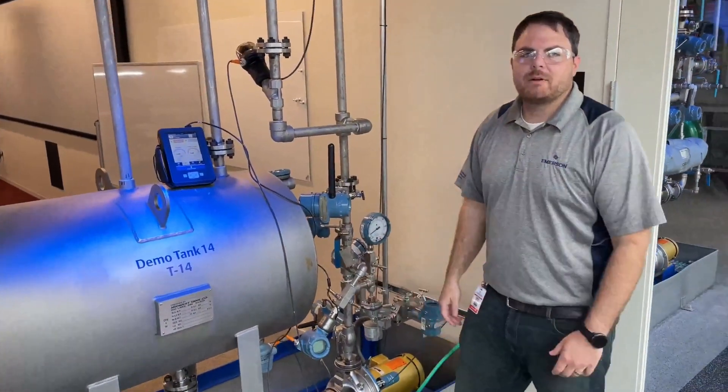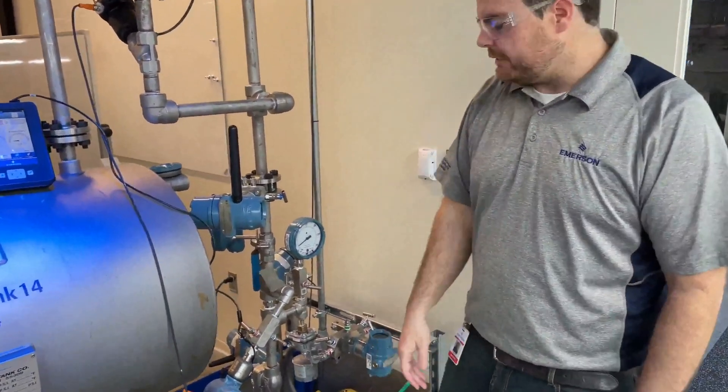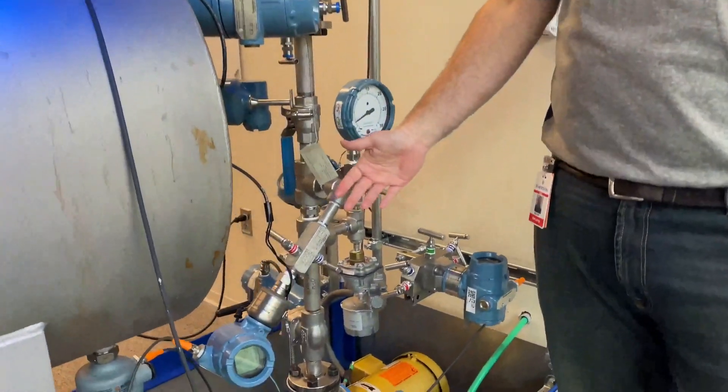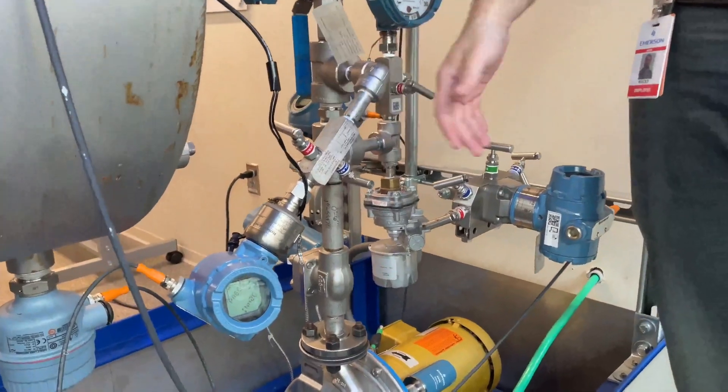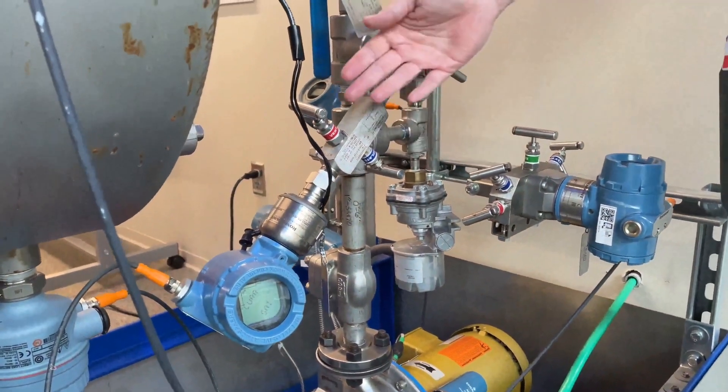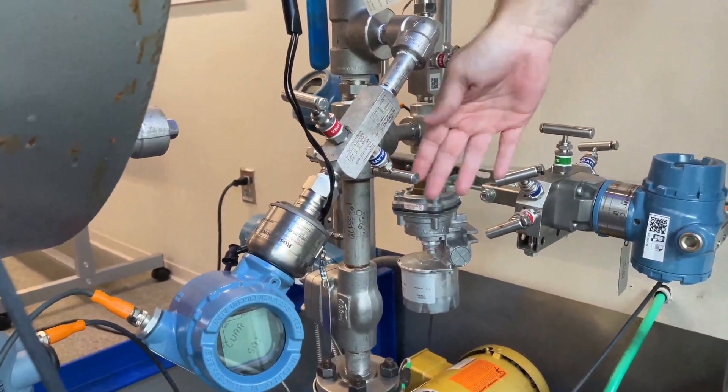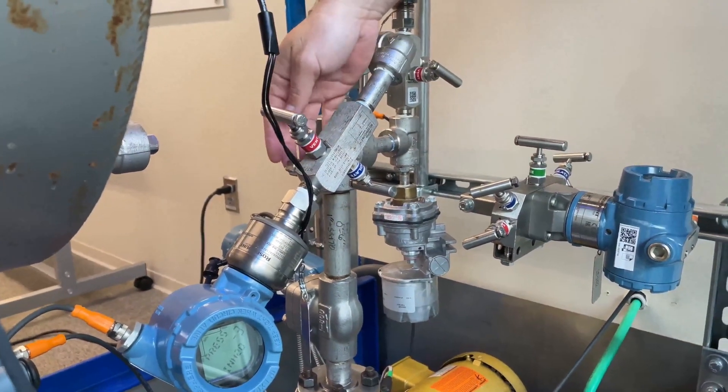All right, welcome back. We now have our transmitter installed out in the field. As you can see, we have now mounted it upside down. We're using that two valve manifold to make sure you can isolate and vent using a vent plug.